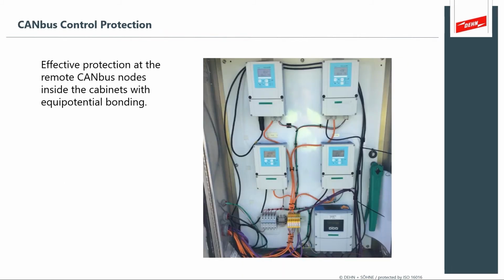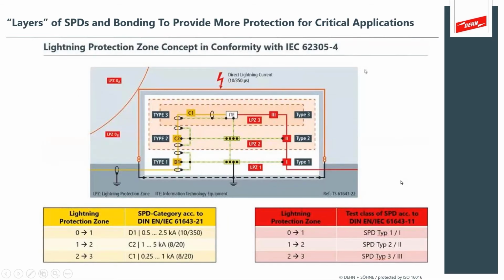You'll see widely distributed CAN bus systems scattered throughout the plant, and these are applications where you want to have the surge protection devices out in the field, and of course back at the marshalling control cabinets. So at a power generation facility, that's an excellent opportunity to pay close attention to the zone that you're operating in.